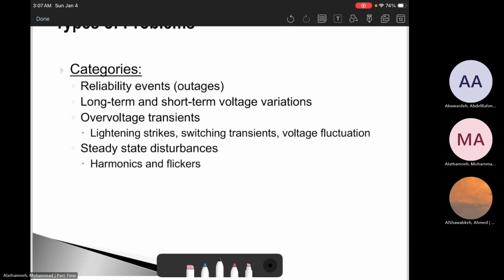The other part is overvoltage transients. Lightning strikes can make transients. Switching, like capacitor switching, can make a big transient. And transmission line switching: if the transmission line was out of service and we re-energize it, it will make a big event. A transient can have a huge amplitude and a very short period because, as we know, a transient is something temporary. But even though it happens for a short period of time, if it has a high magnitude, it can have a bad impact on the power system.